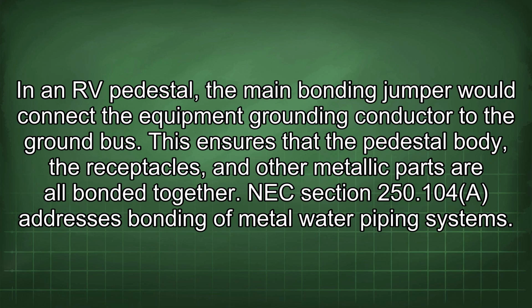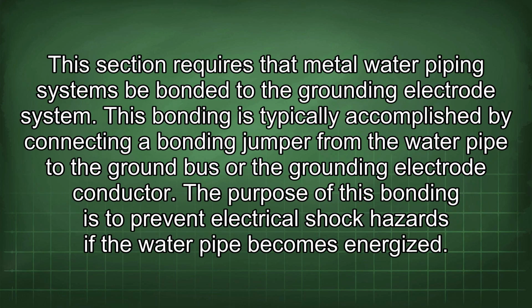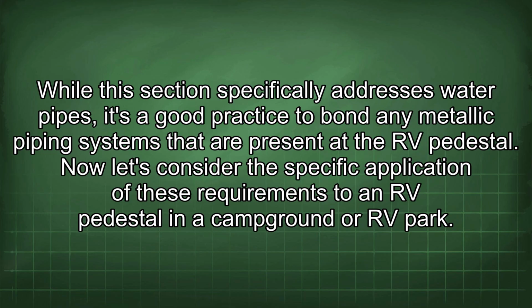NEC section 250.104 addresses bonding of metal water piping systems. This section requires that metal water piping systems be bonded to the grounding electrode system. This bonding is typically accomplished by connecting a bonding jumper from the water pipe to the ground bus or the grounding electrode conductor. The purpose of this bonding is to prevent electrical shock hazards if the water pipe becomes energized. While this section specifically addresses water pipes, it's a good practice to bond any metallic piping systems that are present at the RV pedestal.